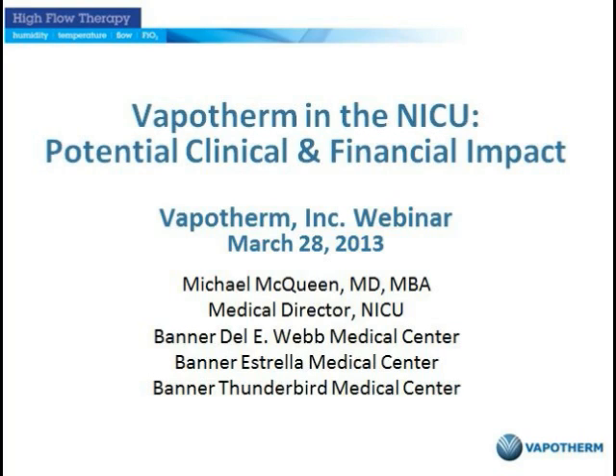How does a Vapotherm differ from the simple humidified high-flow cannula? Probably a couple of answers to that. One is the higher flows to give precise humidity and supplemental FiO2 integration. The Vapotherm's internal integrator device, and I'm sorry, I'm not an engineer on this part of it at all, is now an FDA approved mechanism for delivering those higher flows. And again, given the mechanism of action calling for flows of 5 to 8 liters per minute in the babies, we've not dared to attempt this with regular nasal cannulas. We also have confidence in the Vapotherm provided nasal cannulas that we can size down as the patient size indicates to make sure we're achieving that optimal cannula to nares ratio.